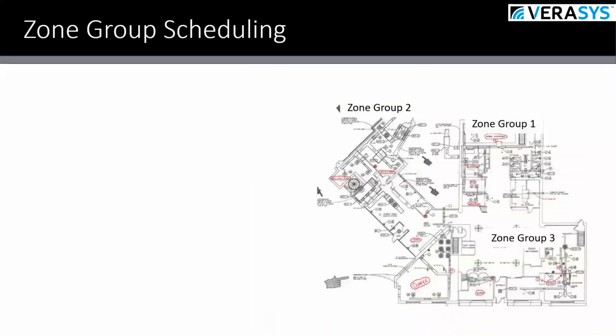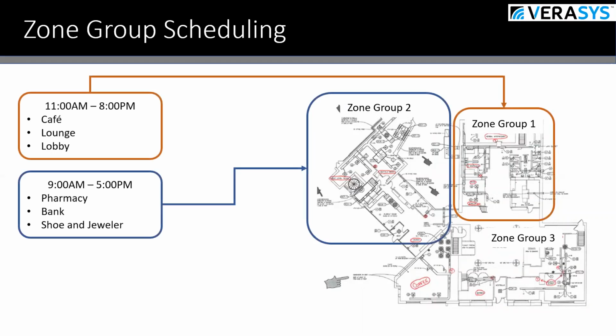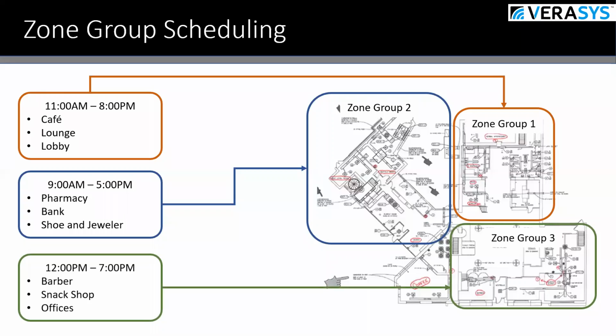Another feature of the new Verasys 4.0 is the zoning system. It can now be set into groups, so each zone can be controlled individually and on its own schedule. For example, in a facility with various departments, a manager may want to occupy zone 3 when it's normally unoccupied, but instead of occupying the entire facility, it can be isolated to that particular zone. This is great for energy savings and shows how Verasys can function as a true energy management system.